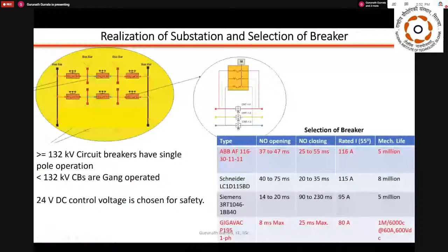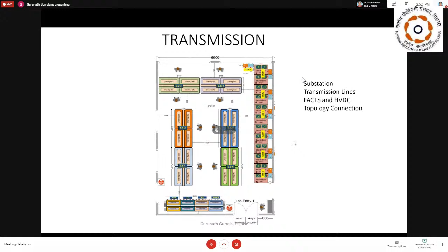Okay. Thank you. So I'm going to the transmission section. Here I will take you through a different understanding of what a substation is, and we have created a substation just like it appears in the field, with substation control panels. Let me show you the different configurations in substations. Predominantly, there are 6 kinds of substation configurations that you use. One is called a single bus, single breaker. That means there will be one live bus where the incoming will come, and then it will go to the load. There will be only one breaker to protect the load.